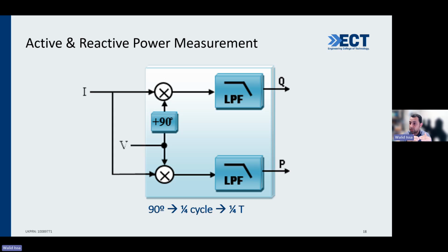Some instruments will stop and you have to decrease it. The regulation of power and voltage can be done by exporting and importing more reactive power. If you export, you can rise the voltage; if you import, you can decrease it. Based on the amount of Q you push or take from that bus, you can contribute to the regulation of that voltage.